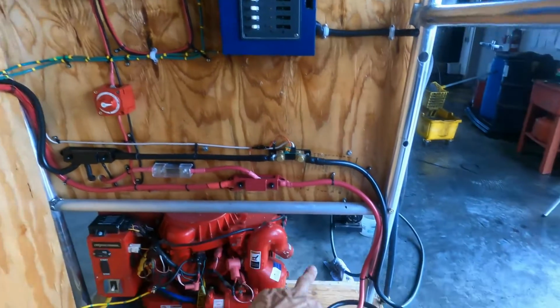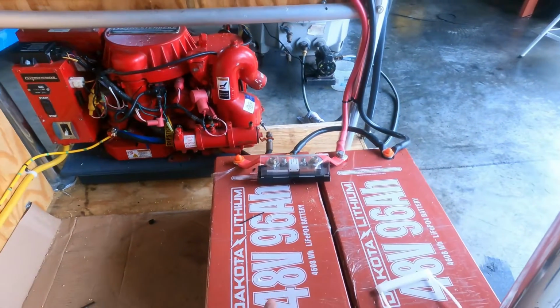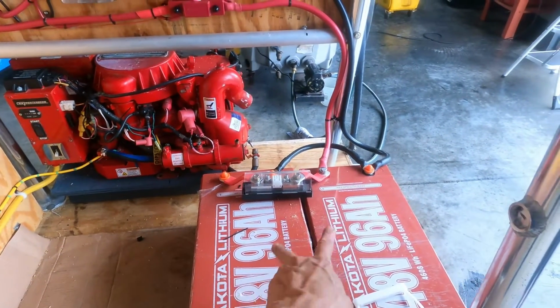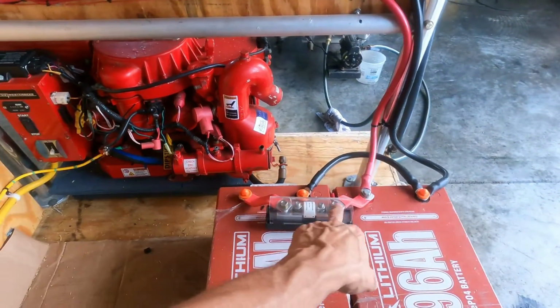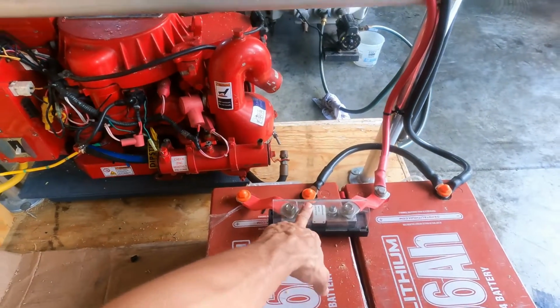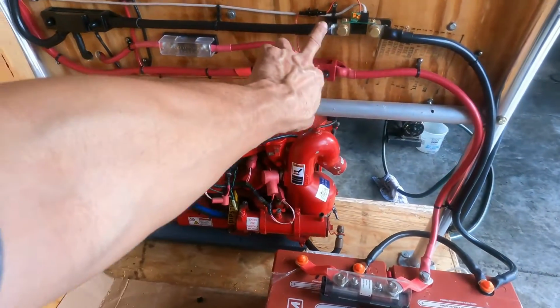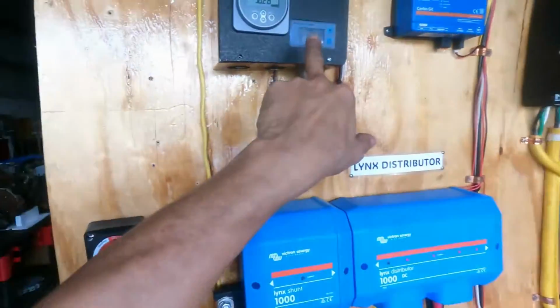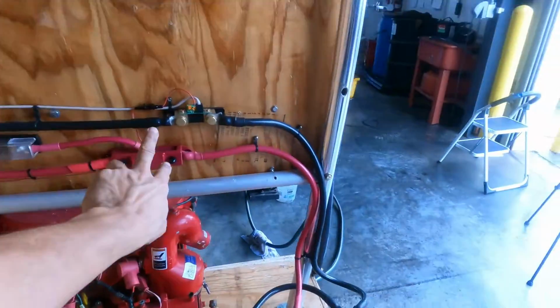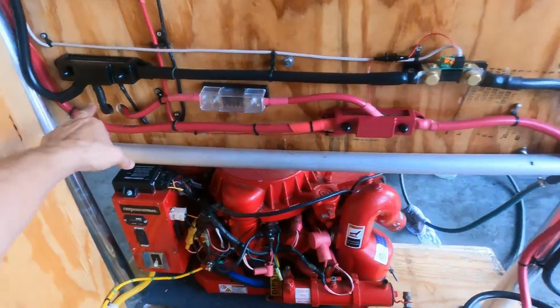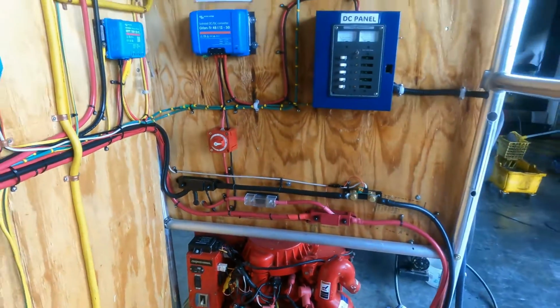And the installation is 48 volts: two batteries of 48 volts, 100 amps, in parallel, negative with negative, positive with positive, and the protection fuse. This is 48 volts, this is the shunt, and this is the gauge for that shunt. 48 volts, and we are going to provide 48 volts here and here for the AC unit.